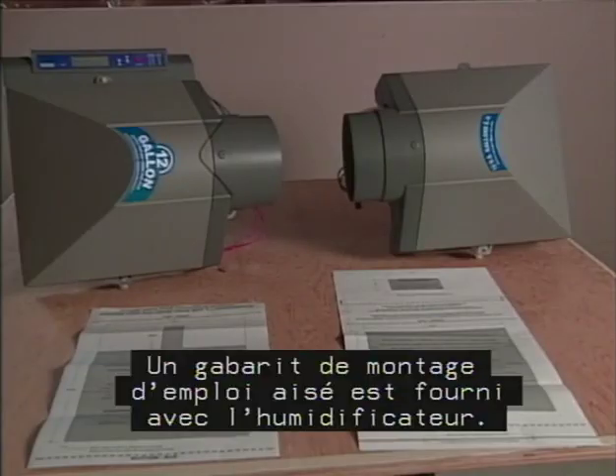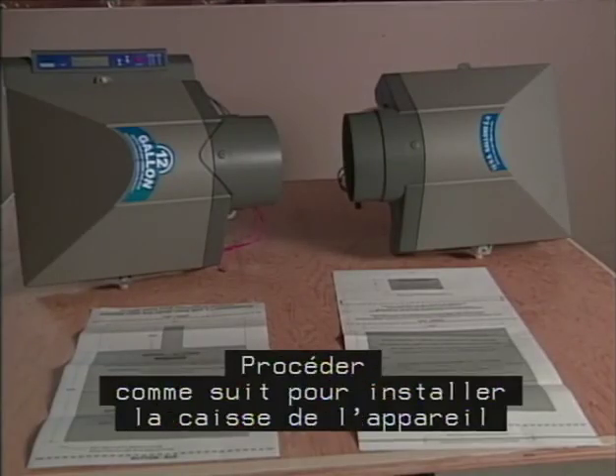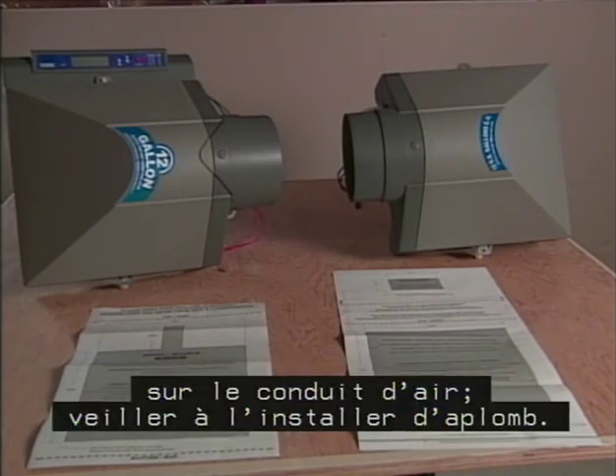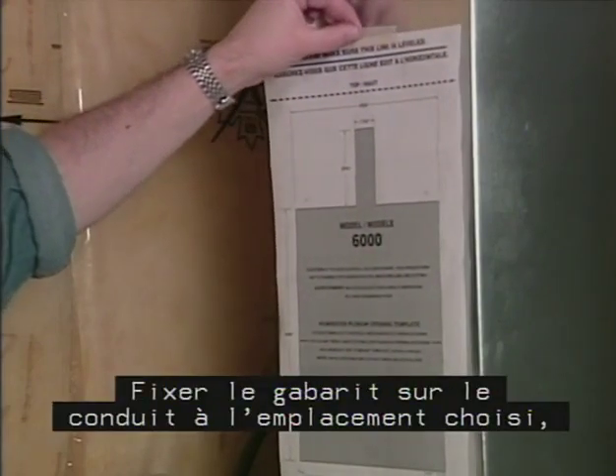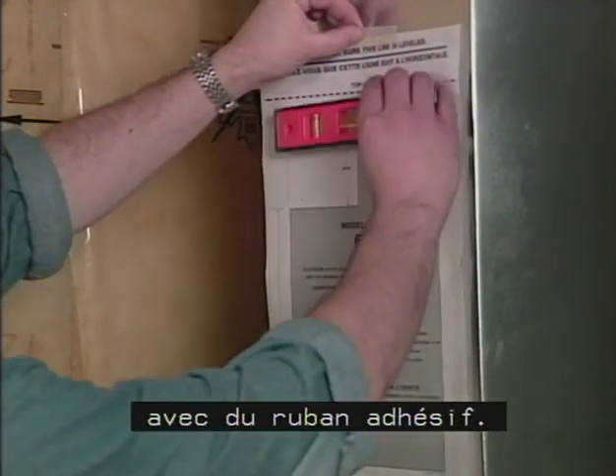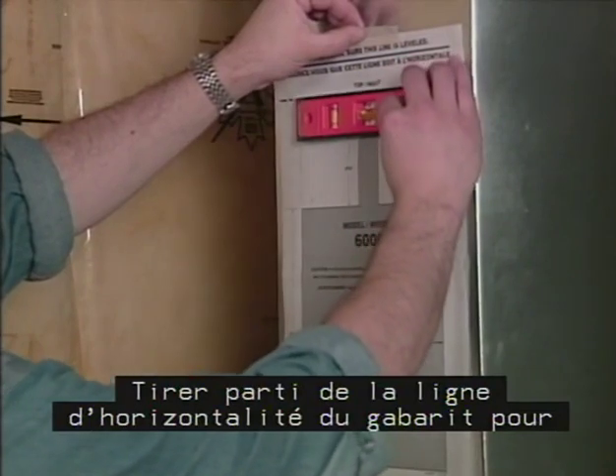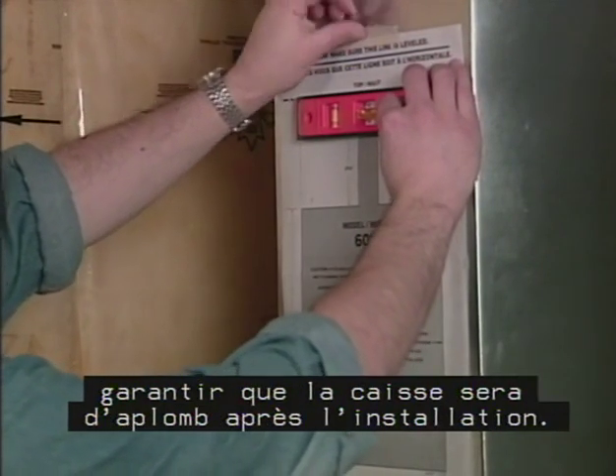Your unit comes with an easy-to-follow humidifier cabinet mounting template. Do the following to install the cabinet on the duct and ensure that the unit is installed level. Use adhesive tape to affix the template onto the duct in the selected location. Use the level line on the template to ensure that the cabinet will be level when mounted.